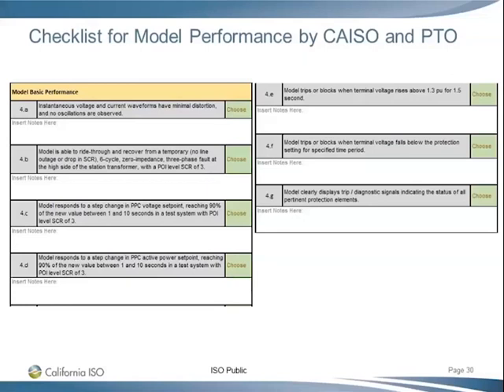Model trips or blocks when terminal voltage rises above about 1.3 per unit. So this could also be yes or no. But typically it should be yes, because I have seen only one or two exceptions that will not trip for high voltage at 1.3. It is very rare that a plant can stand voltage higher than 1.3 per unit. Model trips or blocks when terminal voltage falls below the protection settings.